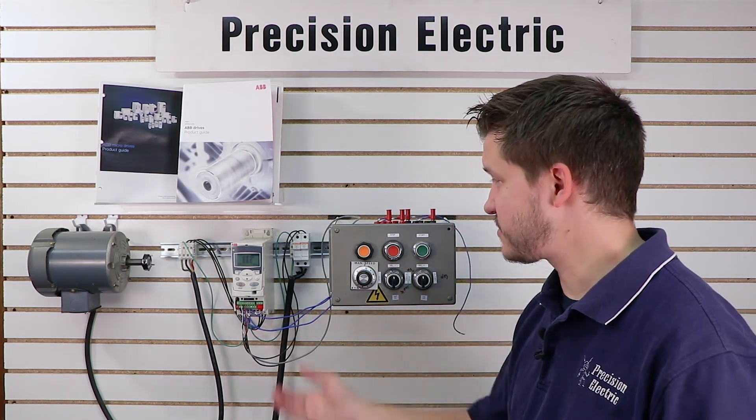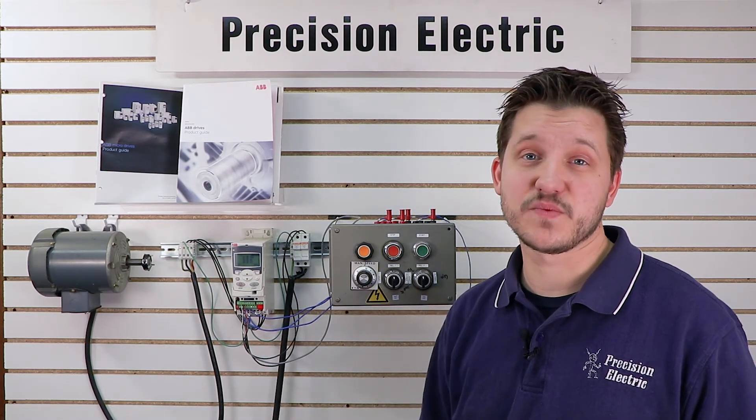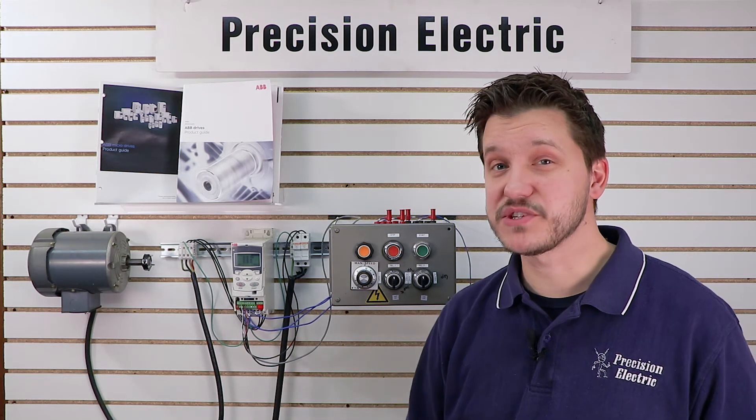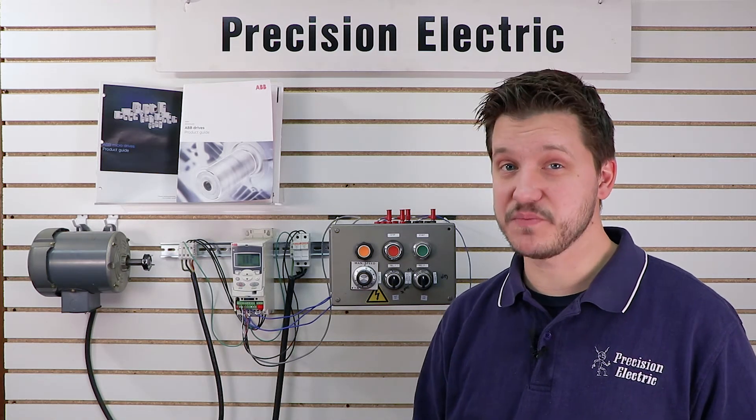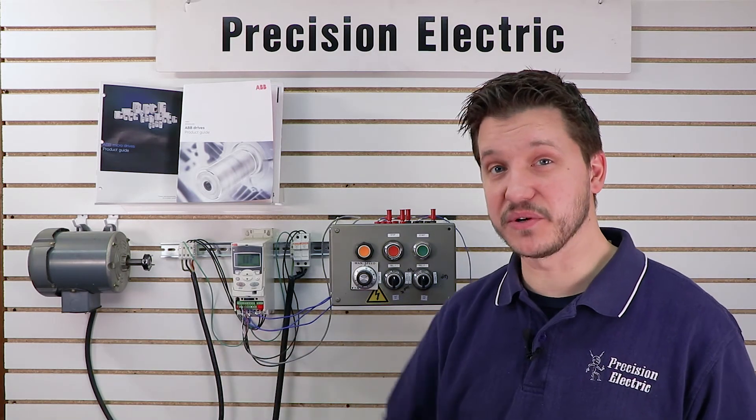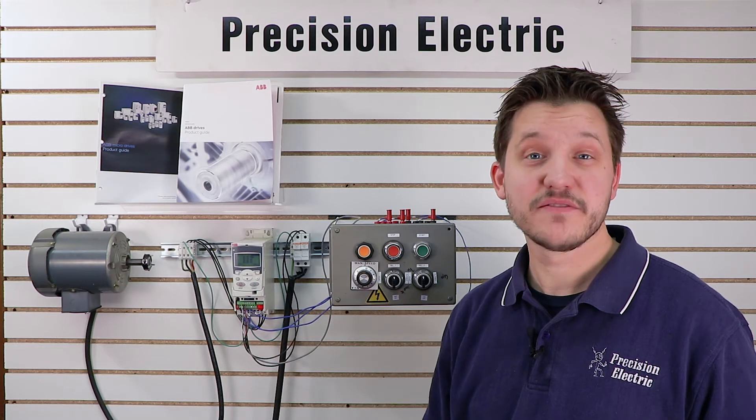But that's all there is to this video. Essentially we have tuned the drive to the motor. Now we can hook the motor back up to the load and run it as we ran it before, and you will get up to pretty much full torque at nearly zero speed. So five percent speed or less, you'll still get the full torque out of your motor, which means you'll get the best possible performance even at lower speeds.